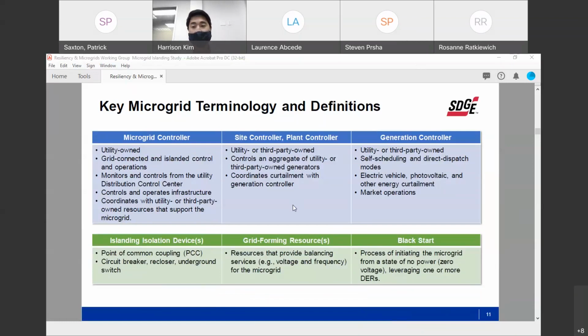The microgrid controller is what allows the utility's distribution control center to operate the microgrid, as well as coordinate with third-party resources or loads or customers behind the meter. On the other side, we have the site or plant controllers, which control the functions of the generators at a specific site. If you imagine a site that might have a battery system, a PV system, maybe some EVs or other resources, the site controller would be the one to operate how each of those work together and their input or output with the grid.